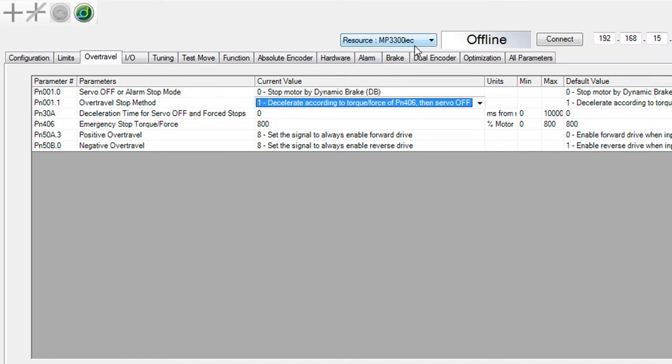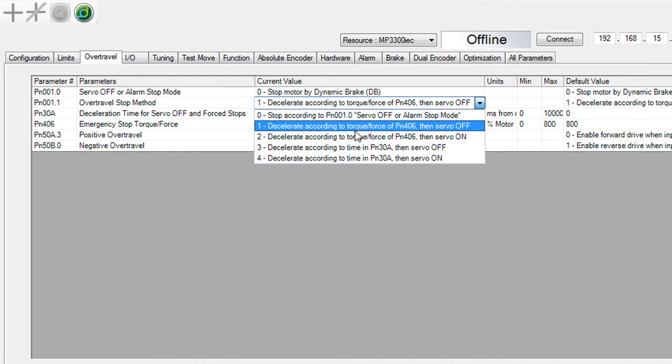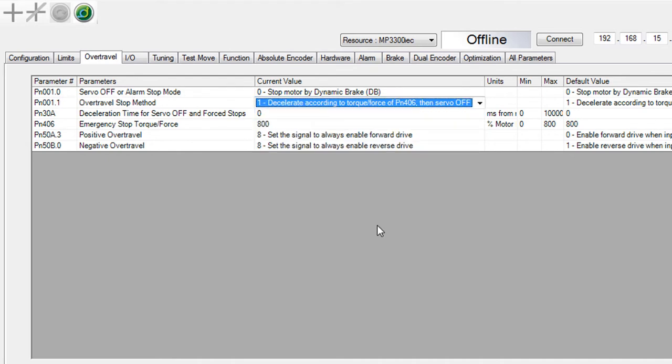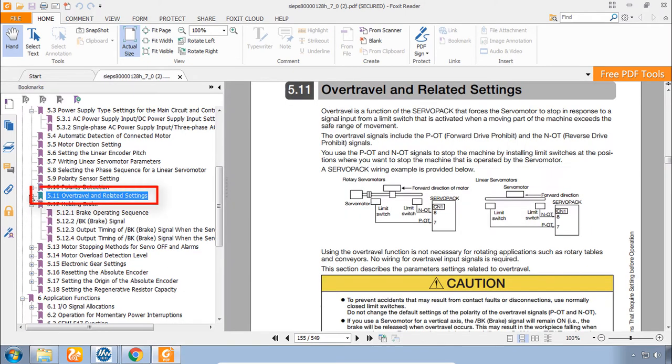It's just the highest torque possible. Well, you can also choose to stop according to this other parameter PN001. And so you choose the stopping method that best suits your application. There's a new one here also the deceleration time. You can have a motor stop over a certain time. Of course more details are always in the manual. This is chapter 5.11 over travel and related settings.